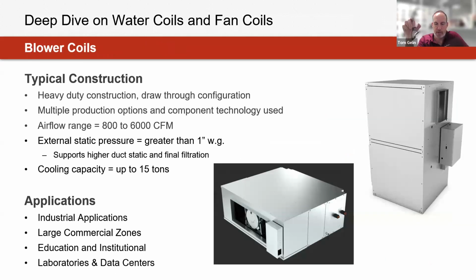Historically, with other suppliers, that high performance fan coil has always given us sound fits, because you've got the same blower, maybe you have an EC motor, maybe you don't, but you've got that 5-pound, 10-pound analogy that we often use, and it's usually in a tight space, and they can be loud. So it's something that, if the engineers are trying to be conservative and put a 1/4 inch of static on it, and then you've got a MERV filter and you've got 8 rows of cooling and heating. Yeah. Oh boy, it's tough.